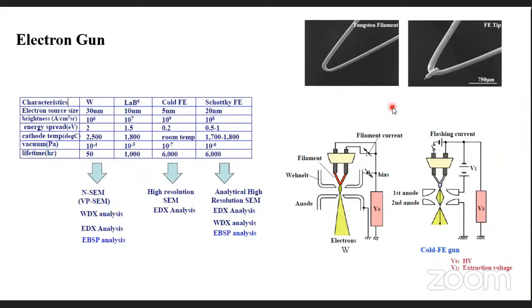About twelve years ago, we bought our instrument for 1.9 crores, and the maintenance is also very hectic. The cold filament can only withstand up to 6,000 hours of use. When you buy it, service engineers will tell you 6,000 hours is the life. We are using it for three to four years — we are an educational institution, so we can't always replace it after 6,000 hours. Now they are giving a quotation of 15 lakhs for changing the gun or filament.